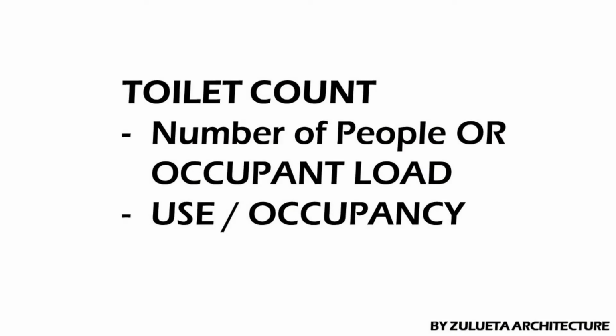The toilet count is based on really two factors: the number of people, or your occupant load, and the use or the occupancy of the space. So for this case, for the restaurant, we have less than 20 seats, plus say 5 staff, so that's 25 users. And the use or occupancy is a restaurant, which in code is an assembly type of occupancy.